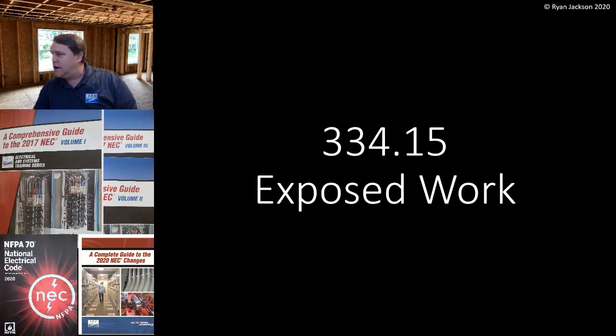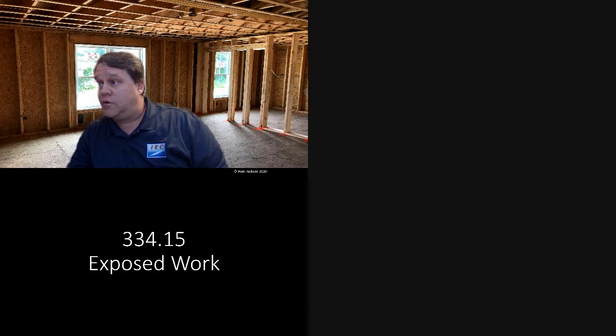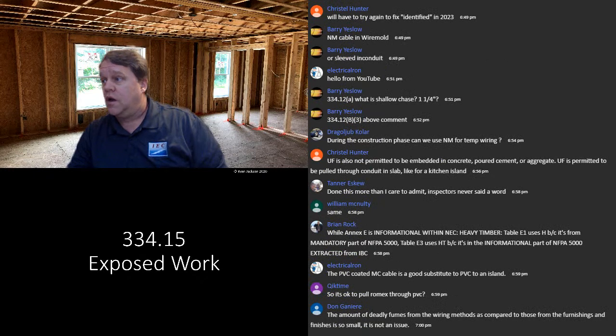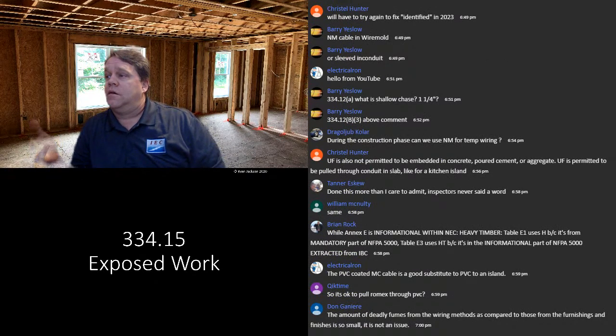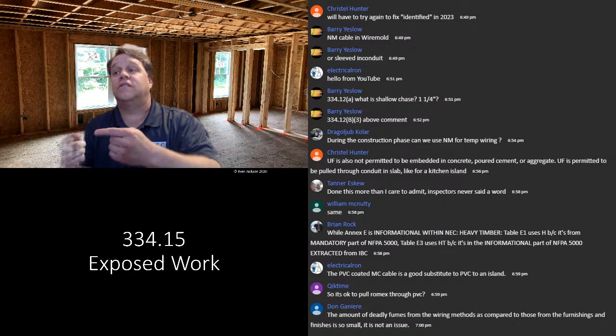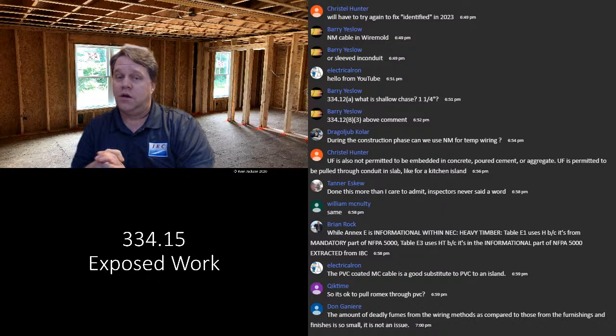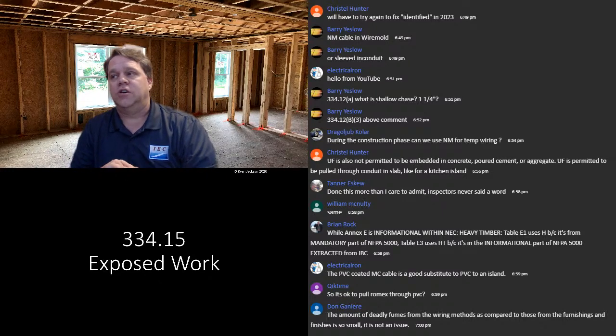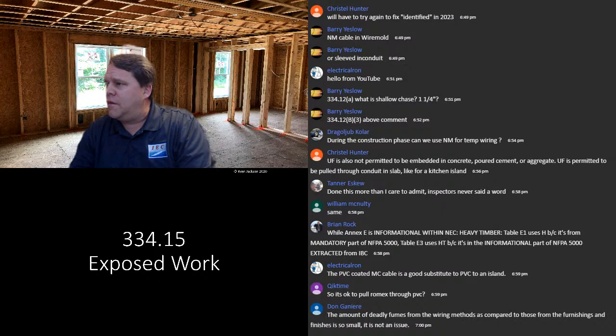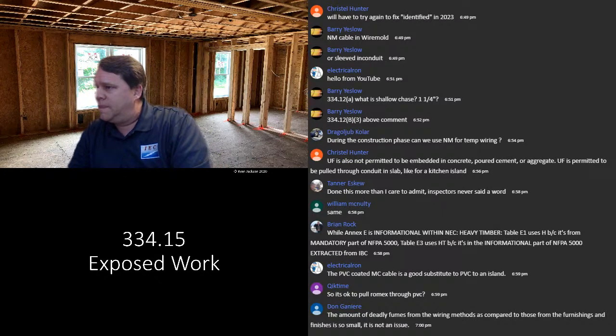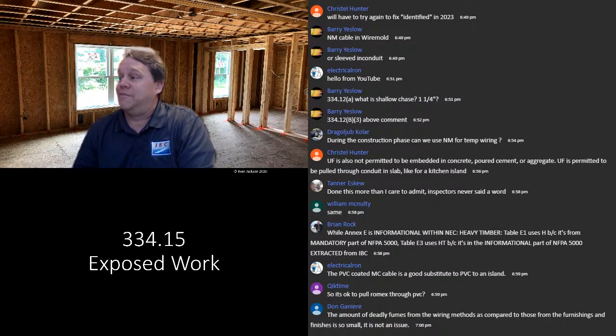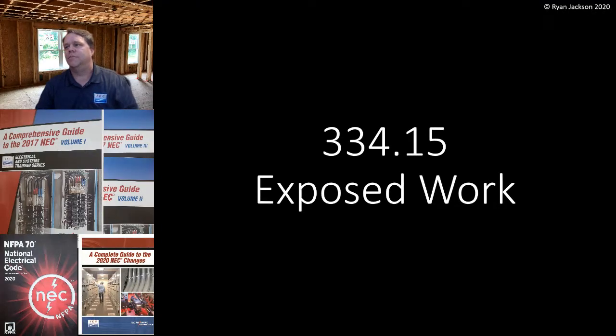Right when I left, it looked like somebody was asking, is it okay to pull NM cable through PVC conduit? If the PVC conduit is in a wet location, then no, because the inside of a conduit in a wet location is itself a wet location. Does that make sense? Don says the amount of deadly fumes from the wiring methods compared to those from the furnishings is so small. I agree. I think the plenum rated stuff, to a certain extent, is a little bit overblown. I hate to admit that, but I agree.